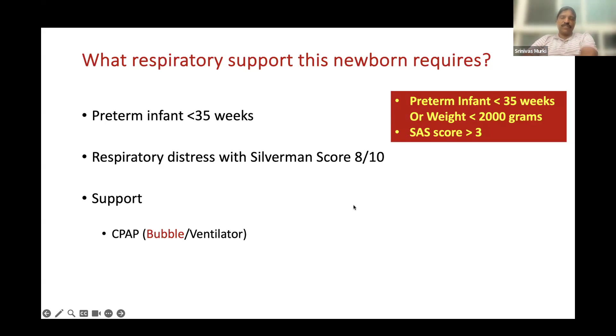So how do we give CPAP or bubble CPAP? These are the mandatory things you need. You need pressurized air, you need pressurized oxygen, either central oxygen or cylinder oxygen. Then you need a blender. So you need the connections for air and oxygen: an air connector, an oxygen connector, a blender, and then a flow meter. Flows are the things which will generate pressures; you need flows to generate pressure in the circuit and pressure in the lungs. And one very important thing, whether it is for HFOV, conventional ventilation or CPAP, you need a good humidifier, which is able to deliver the gas at the nose at 37 degrees and 100% humidity.